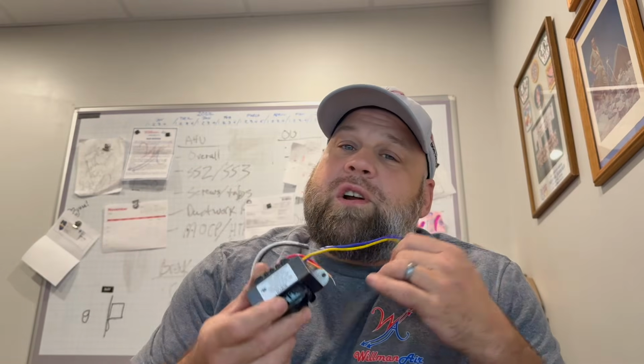A lot of you who have a little bit of experience knew right when I said she changed the thermostat by herself, you knew what the problem was, okay? She did not turn off her heat breaker. Your heat breaker that feeds your high voltage going to your indoor unit also feeds into this transformer, and that gives you your 24 volts going to that thermostat. So there's always 24 volts AC going to that thermostat until you turn off that heat breaker. She did not turn off the breaker.